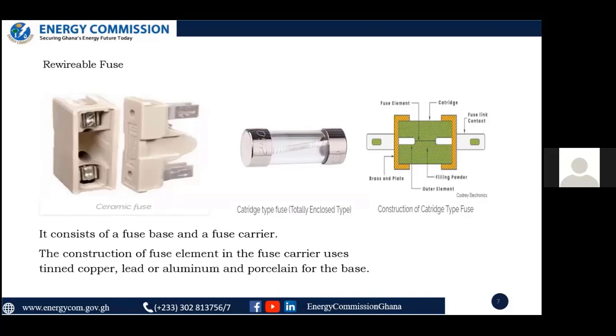When that happens, we have to rewire the fuse, meaning we need to find an equally gauged melting element. So if the gauge of the wire is, say, 0.5 millimeter square, you have to find another 0.5 millimeter square of the same fuse element and rewire the fuse. It's quite technical, so once it's been installed by an electrician, even some electricians don't have the technical know-how to gauge the wires and rewire the fuse when it gets blown.